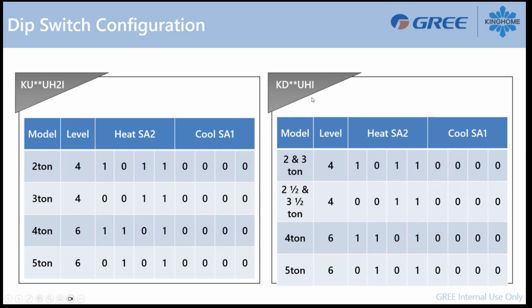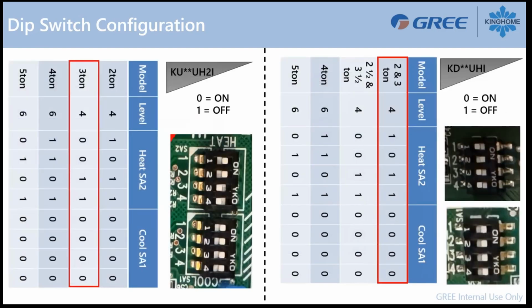On a KD air handler, you will have the same kind of configuration, but a 2-ton and a 3-ton is using speed 4 as the default speed, and you will find the same configuration here. A 2-and-a-half-ton and a 3-and-a-half-ton, speed 4 as default, and this configuration here. So on, off, off. 4-ton, 5-ton, we're using a default speed 6 and this kind of configuration. And to help you understand it, I suggest you just flip your user manual on the side like this. And so you will find the configuration much easier to understand.